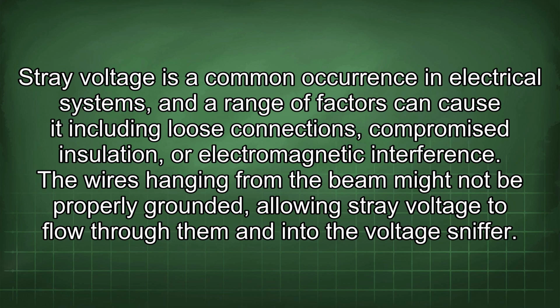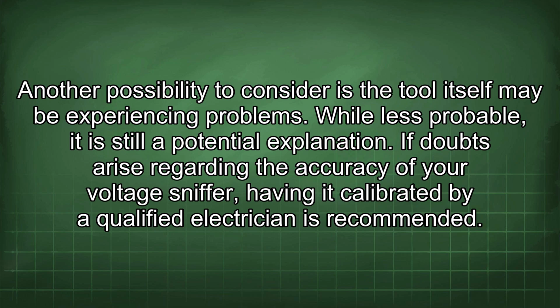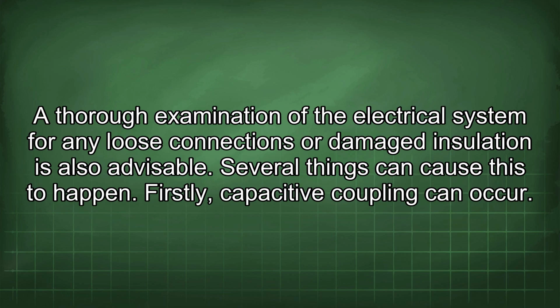The wires hanging from the beam might not be properly grounded, allowing stray voltage to flow through them and into the voltage sniffer. Another possibility to consider is the tool itself may be experiencing problems. While less probable, it is still a potential explanation. If doubts arise regarding the accuracy of your voltage sniffer, having it calibrated by a qualified electrician is recommended. A thorough examination of the electrical system for any loose connections or damaged insulation is also advisable.